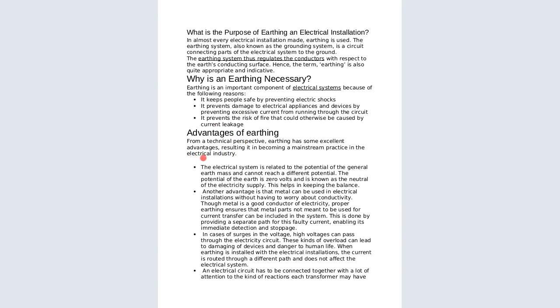So advantages of earthing. The following are some of the advantages of earthing in an earthing system. So from the technical perspective, earthing has some excellent advantages, resulting in becoming the mainstream practice in the electrical industry. So one of the advantages of earthing is the electrical system is related to the potential of the general earth mass and connected and cannot reach a different potential. So the potential of the earth is zero, normally 0 volts, and is known as the neutral of the electrical supply. So this helps in keeping the balance.